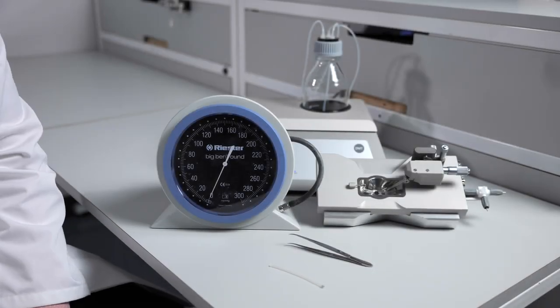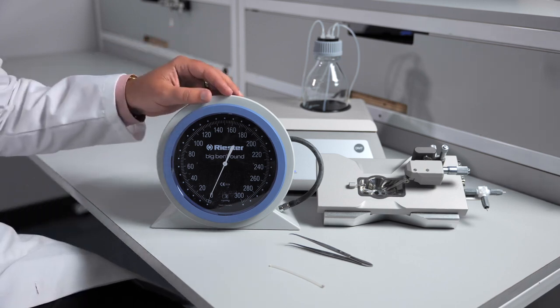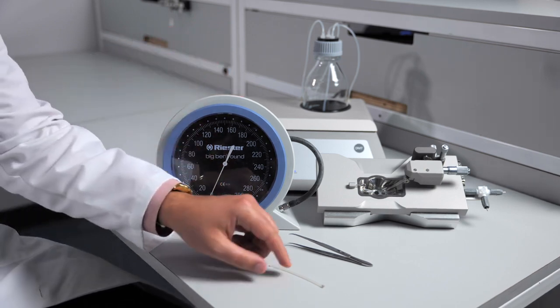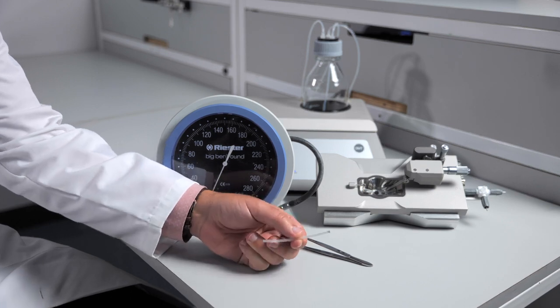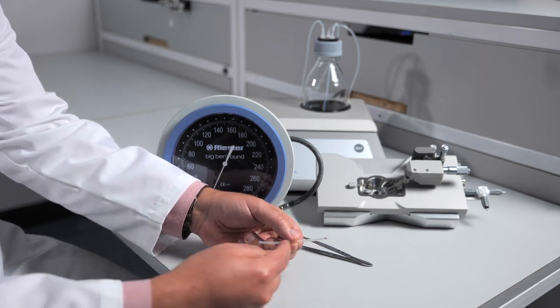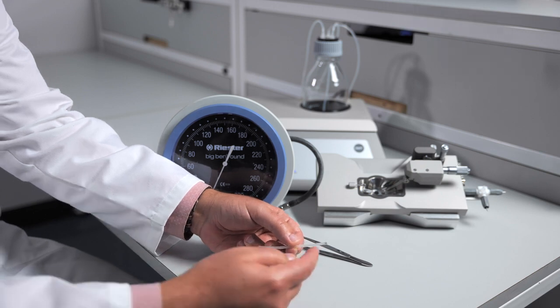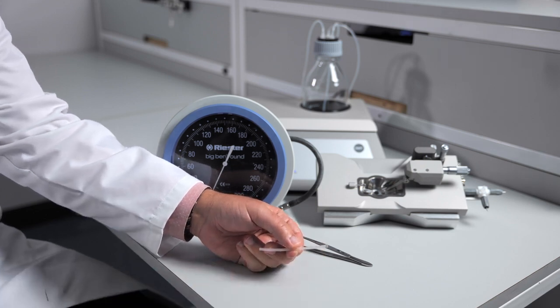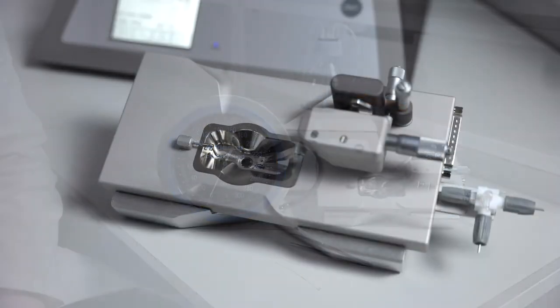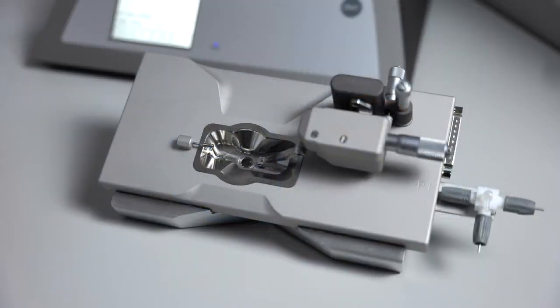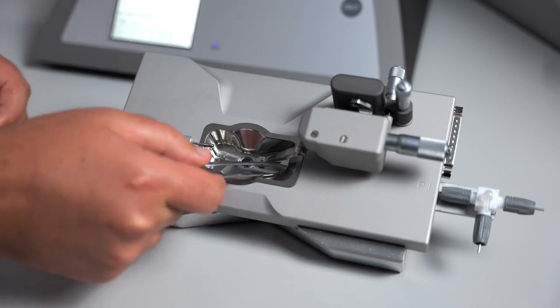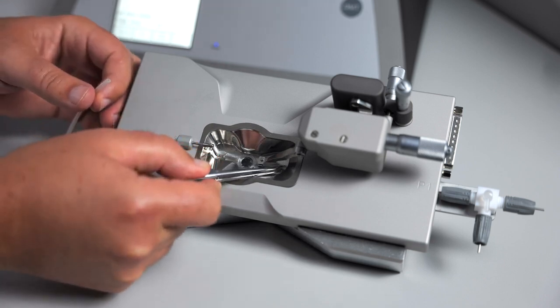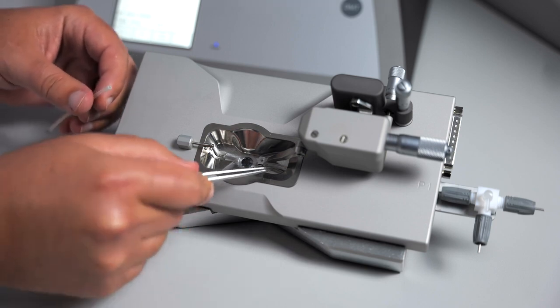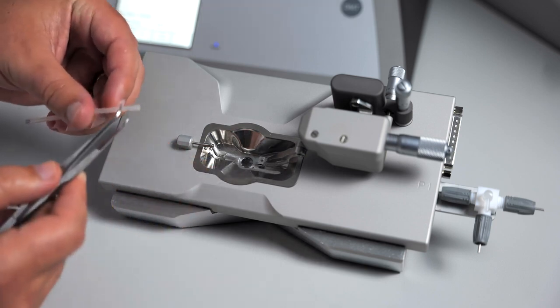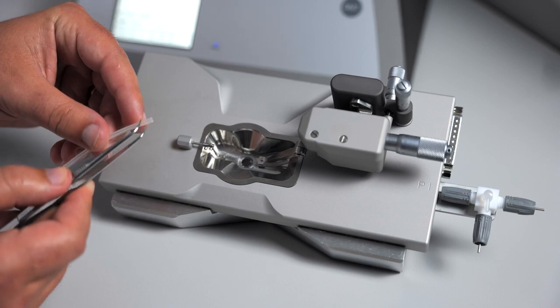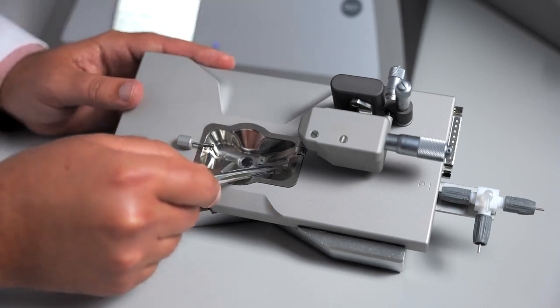In order to perform the pressure calibration, you will need your big ben manometer and the 114P Blind-sac calibration shunt. This is slightly different than other pressure calibration shunts, as this shunt has a plugged end. To prepare the chamber for the calibration, you will need to disconnect the P1 tubing inside the chamber, and then you will take the non-plugged end of your calibration shunt and replace that tubing.